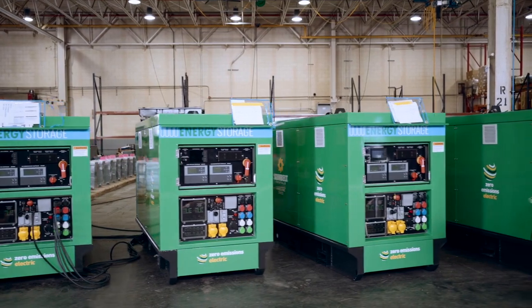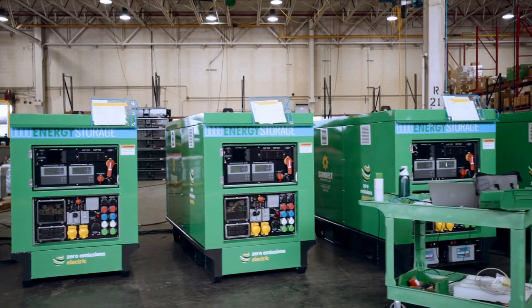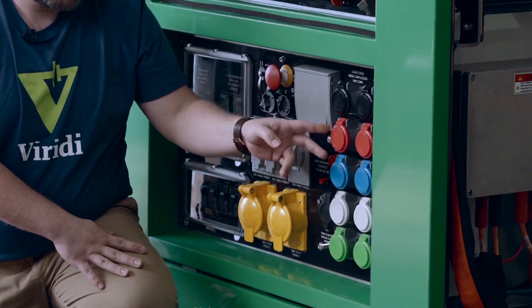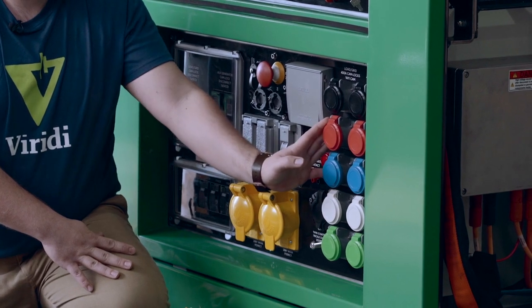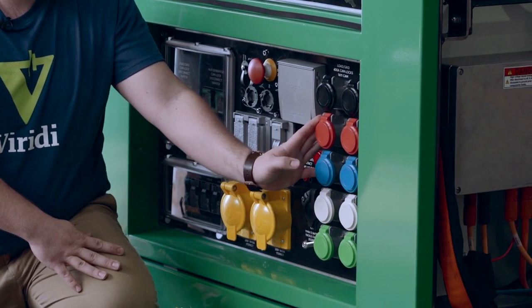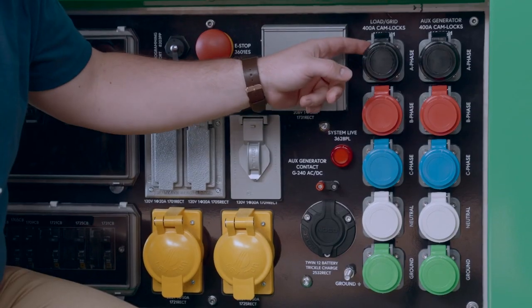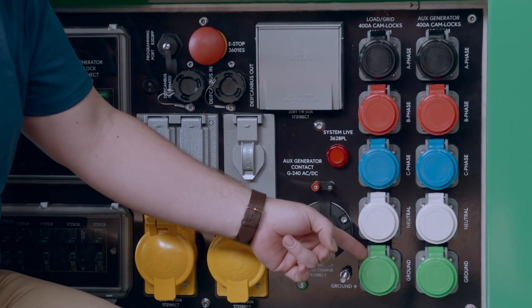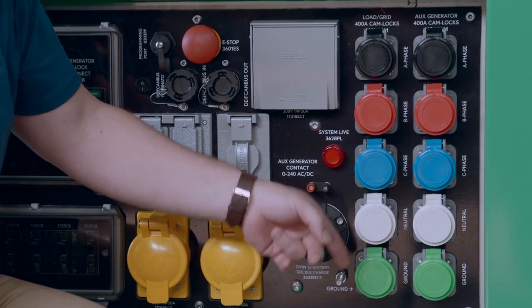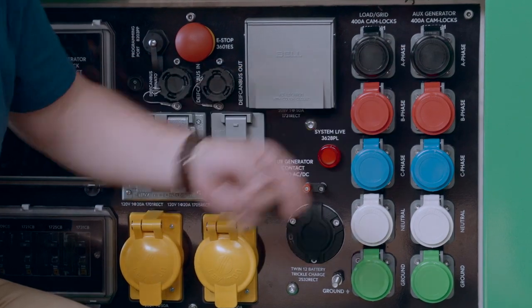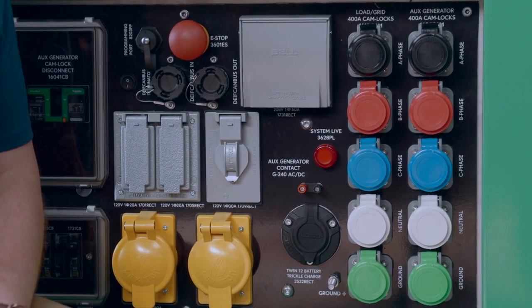The last two connection points I want to talk about are cam lock connections. Typical, you have your 400 amp cam lock connection for 3-phase, selectable 480 volts or 208 volts. The first and left-hand side one is for your load/grid connection. Your second one, your right-hand side, is for your auxiliary generator for your generator hybrid setup.